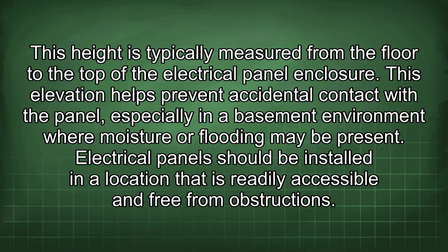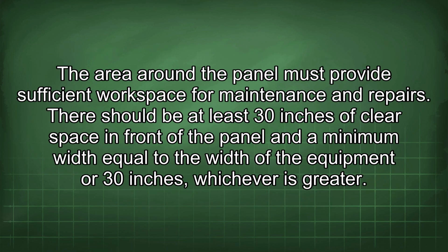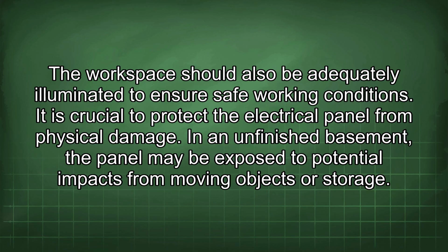This elevation helps prevent accidental contact with the panel, especially in the basement environment where moisture or flooding may be present. Electrical panels should be installed in a location that is readily accessible and free from obstructions. The area around the panel must provide sufficient workspace for maintenance and repairs. There should be at least 30 inches of clear space in front of the panel and a minimum width equal to the width of the equipment, or 30 inches, whichever is greater. The workspace should also be adequately illuminated to ensure safe working conditions.